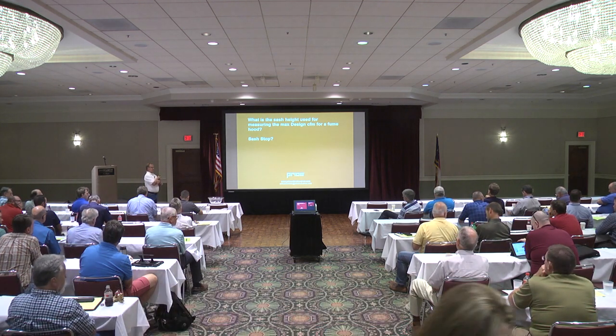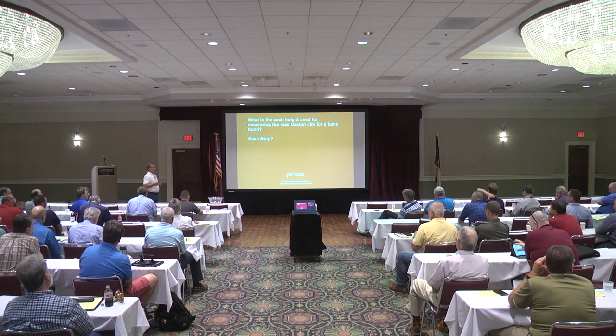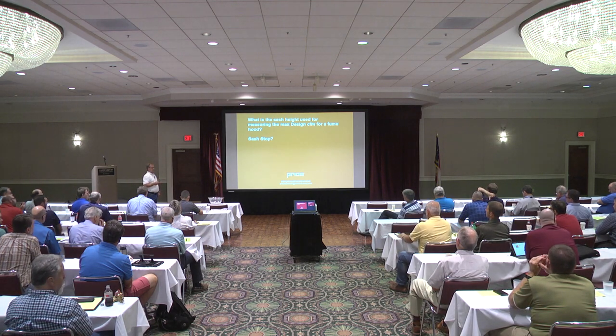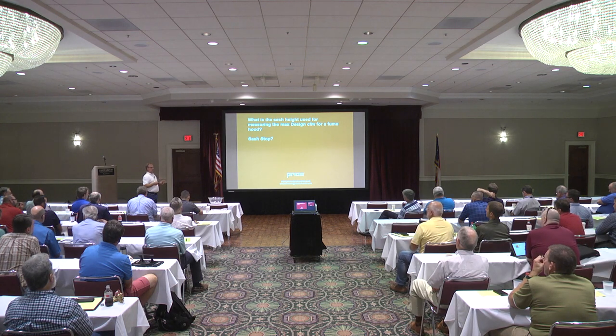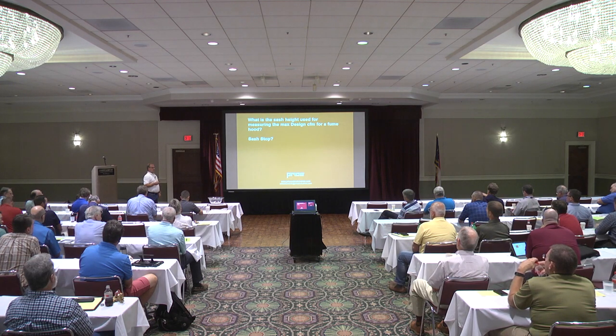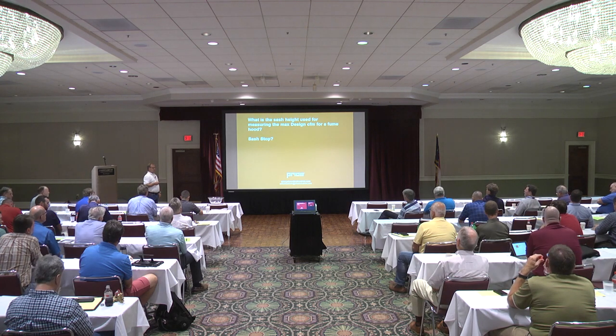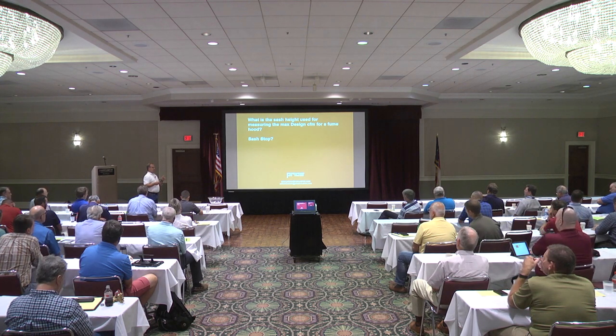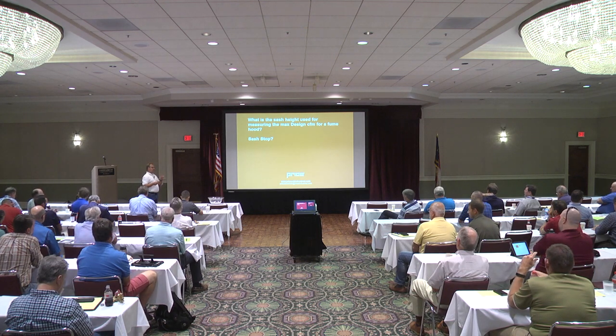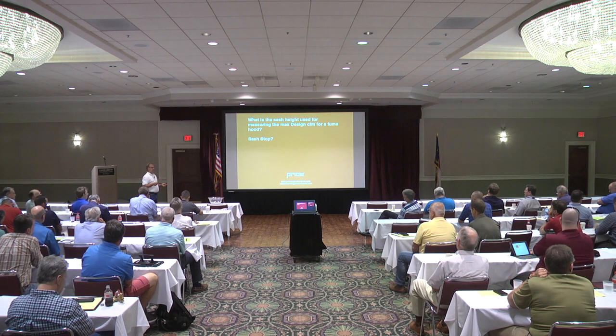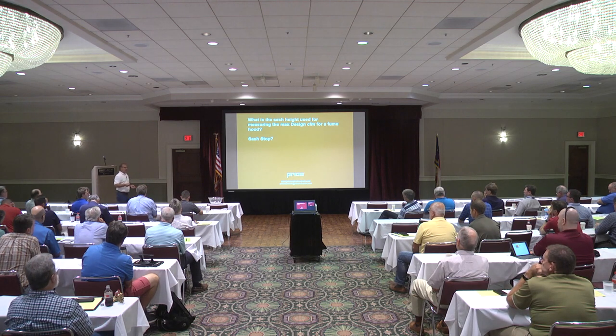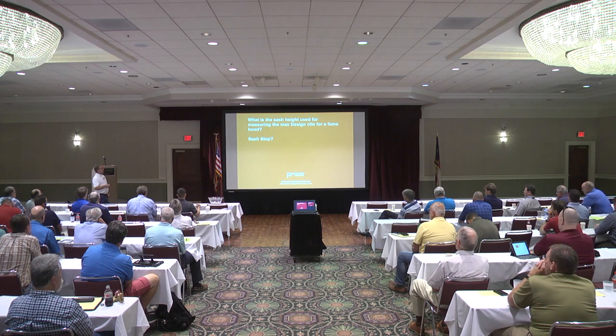That's the working height. As a certifying agent or as test and balance? Test and balance. So you had multiple CFMs then for that one hood. They were only using it at one height per type of hood. So for that hood, we would measure it at that height. If it was 12 inches, it would be 12 inches. But the CFM associated with that 12 inches was probably on the schedule for that hood. Yes. Okay, so they did their design properly. That's a good thing. It's not seen enough.